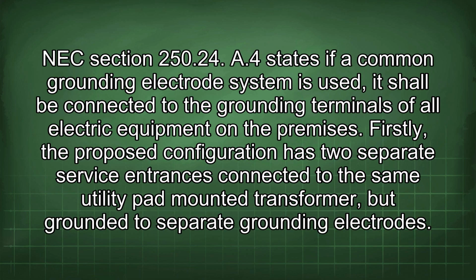NEC Section 250.24 A4 states if a common grounding electrode system is used, it shall be connected to the grounding terminals of all electric equipment on the premises.